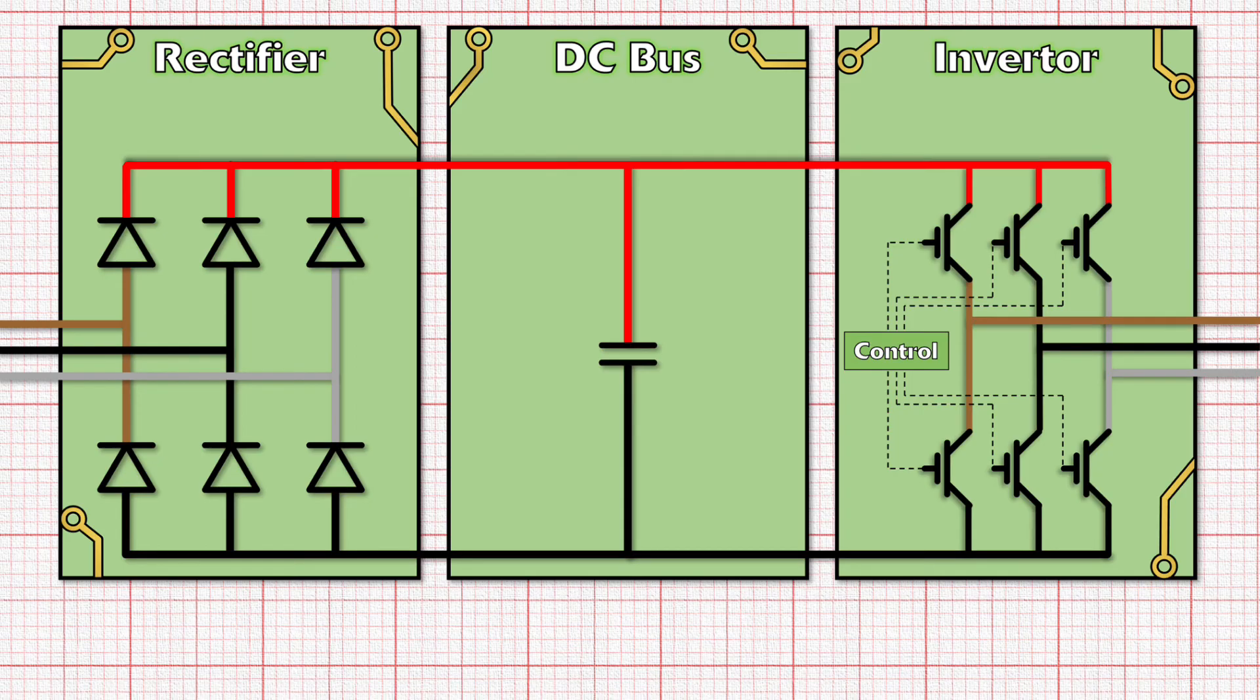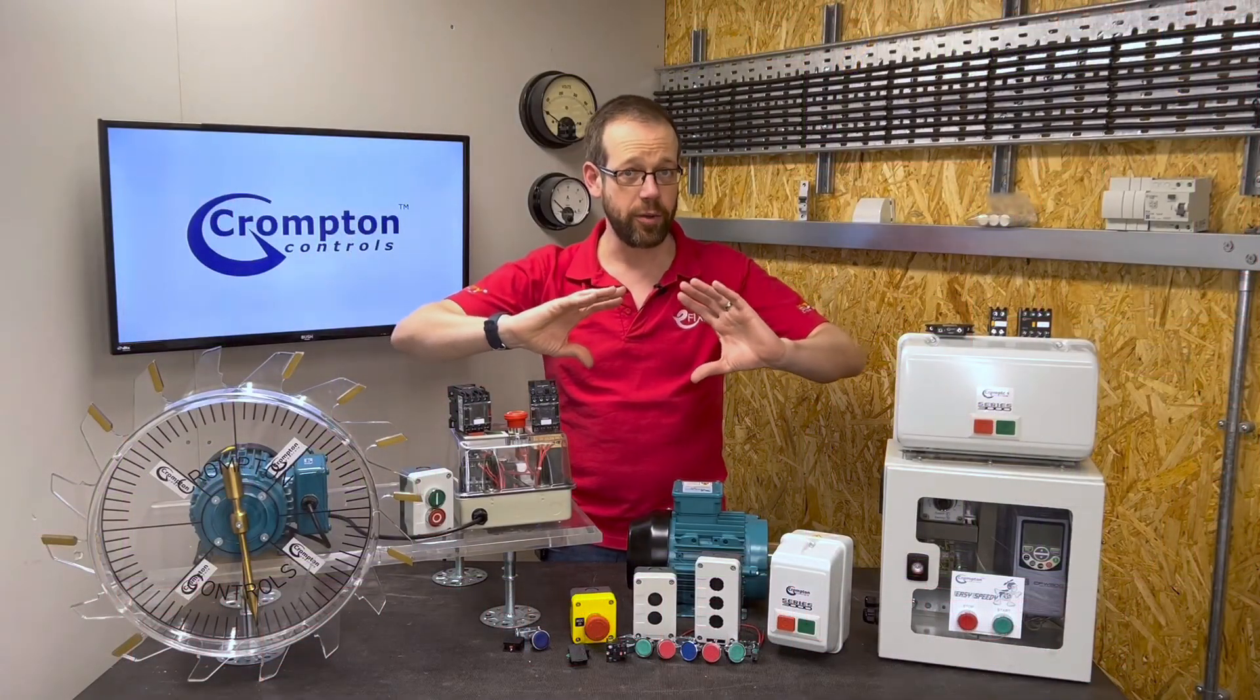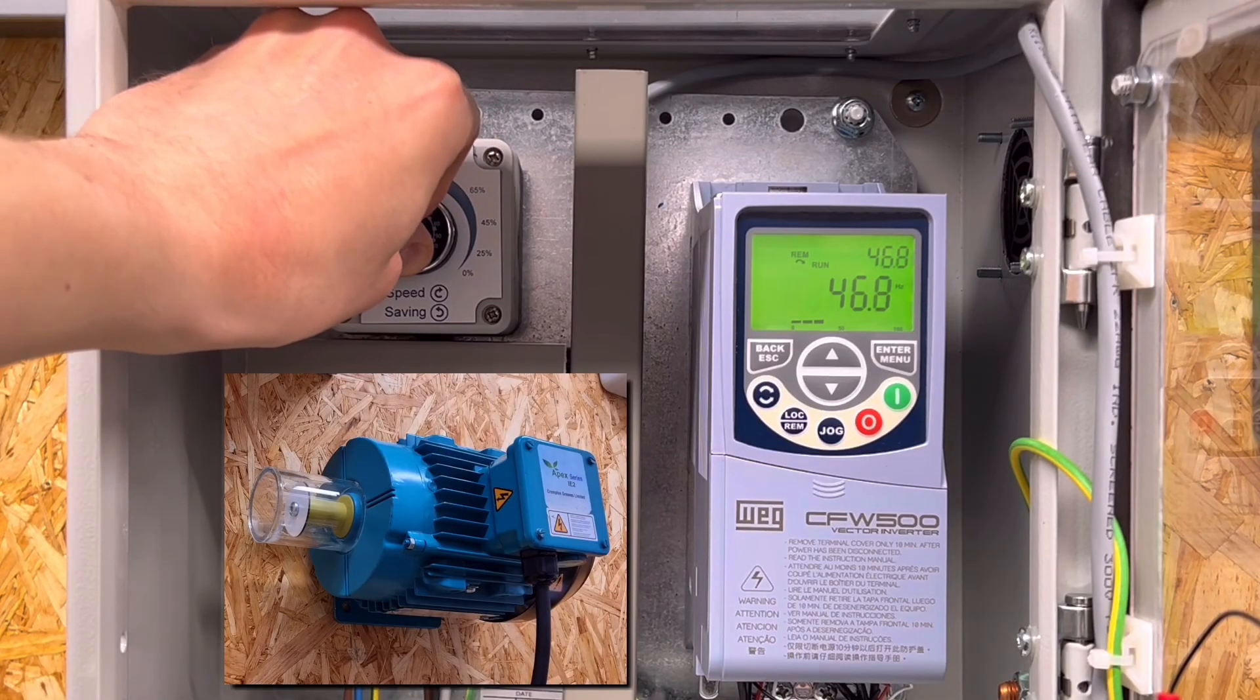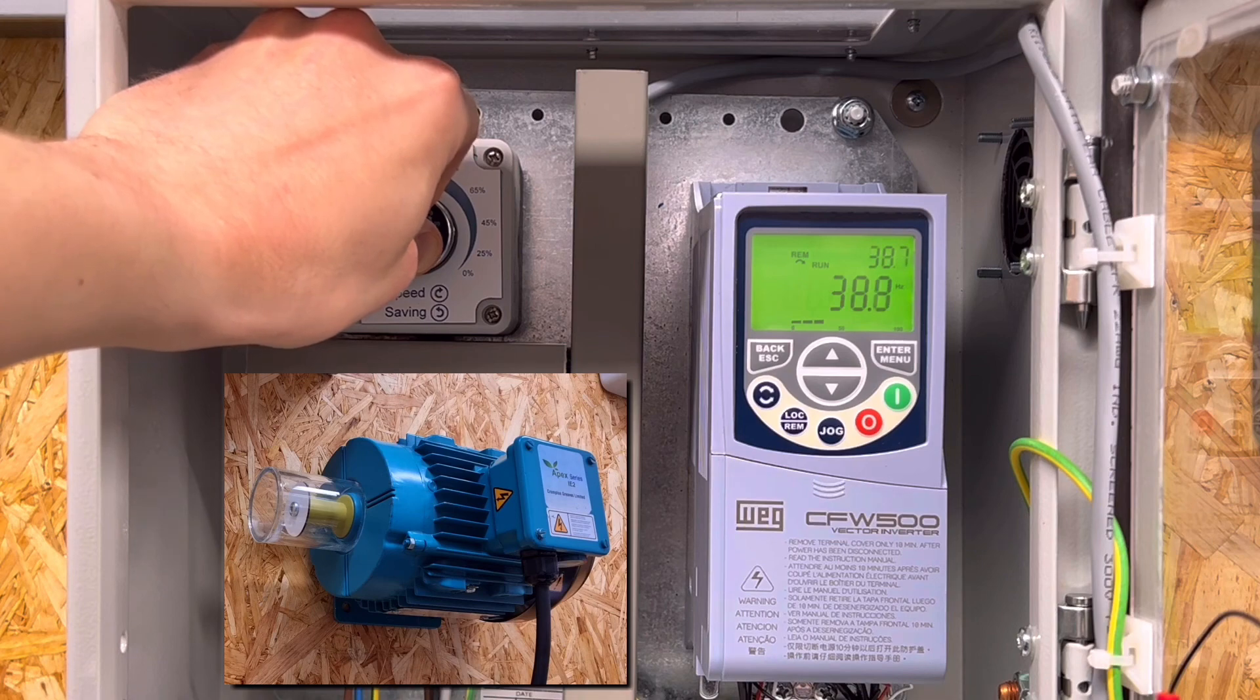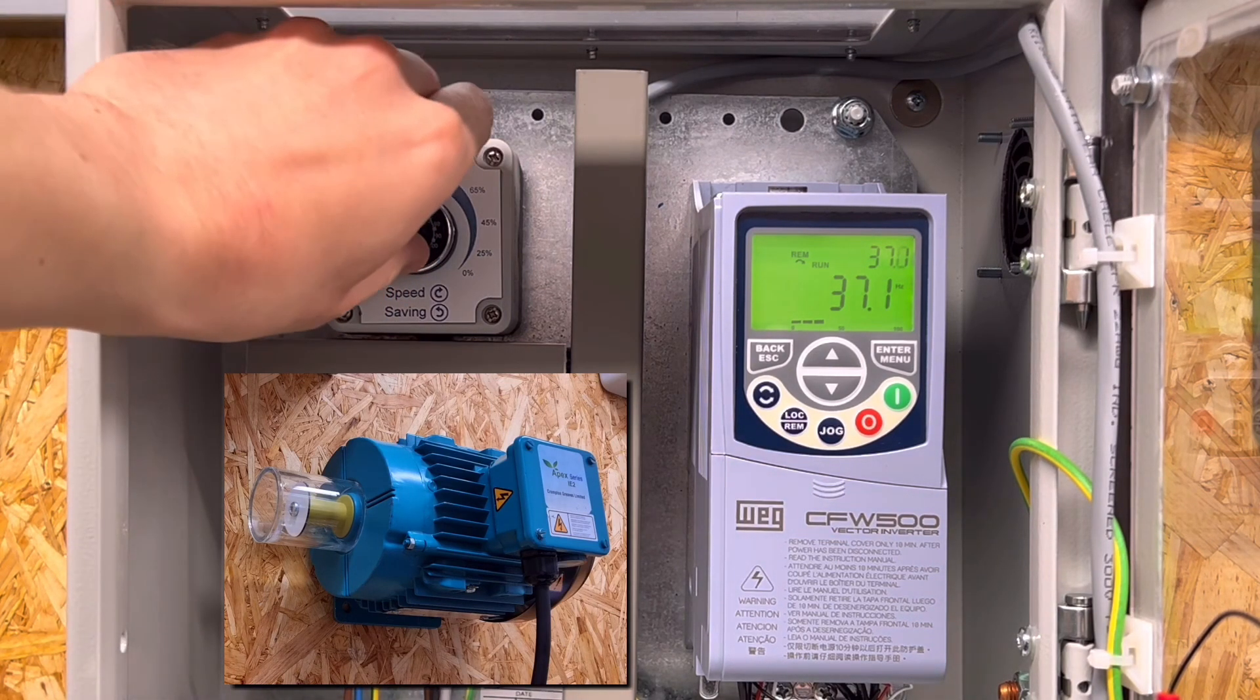And remember, in the first part of the video we said the speed at which the magnetic field in the motor turns depends on the frequency of the three-phase supply. So by varying the frequency of the output from the drive, we can control the speed of the motor.